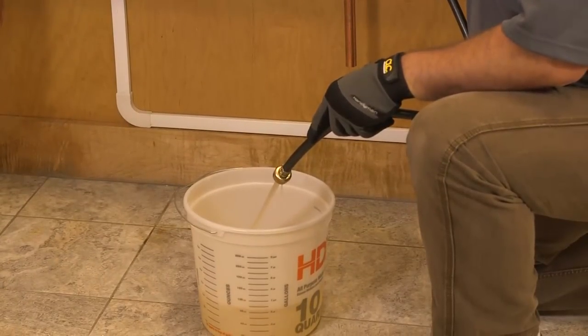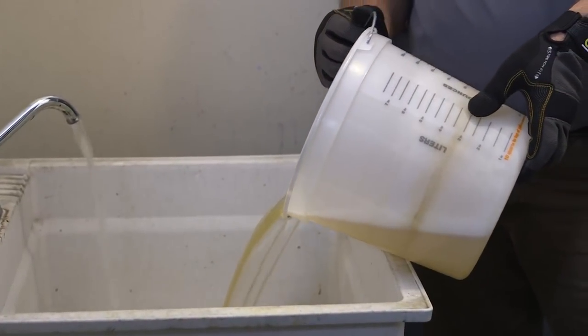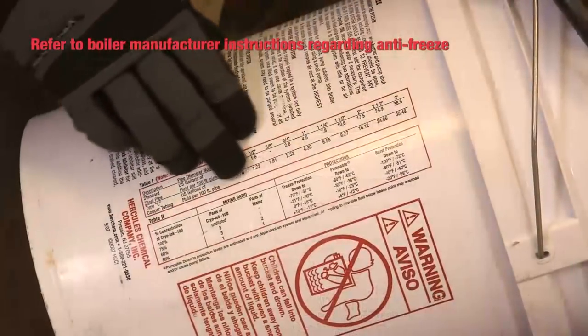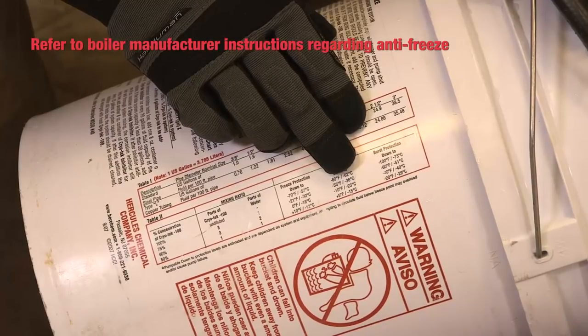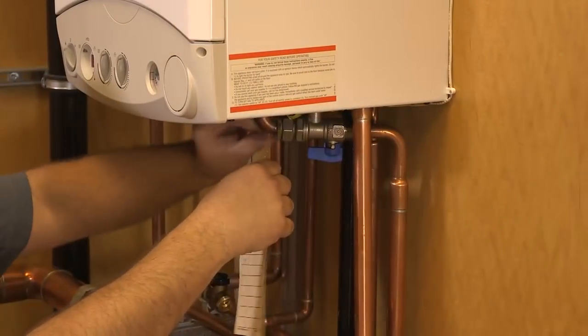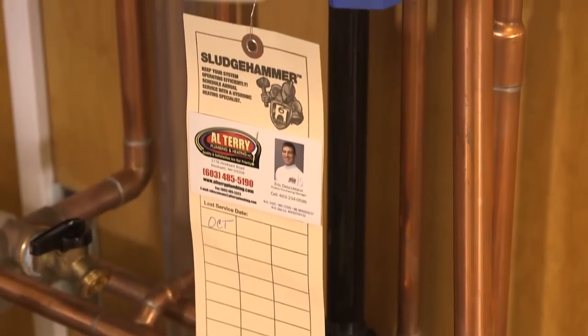Completely drain and flush the system to remove system debris. Sludge Hammer products are safe for sewer disposal. Refill the system with water, adding antifreeze and Sludge Hammer Universal Corrosion Inhibitor per that product's instructions. Check corrosion inhibitor and antifreeze levels annually. Be sure to fill out and attach a Sludge Hammer service card as a reminder for annual system maintenance.